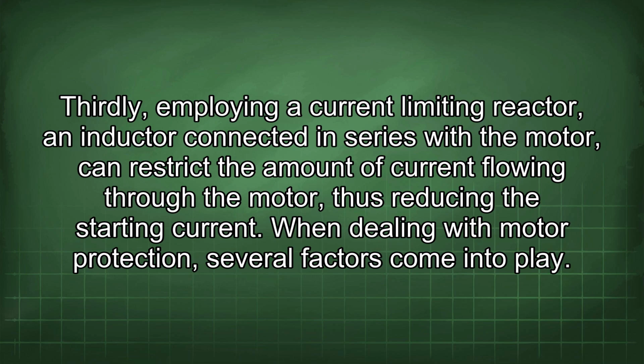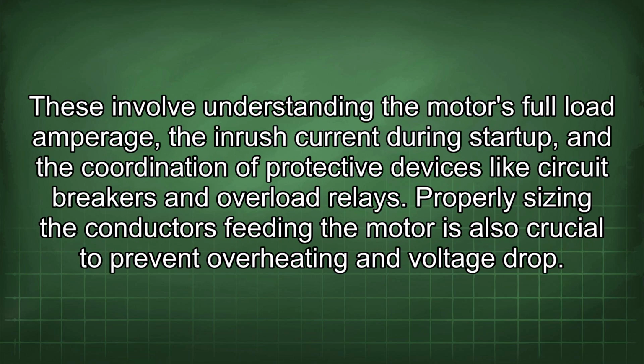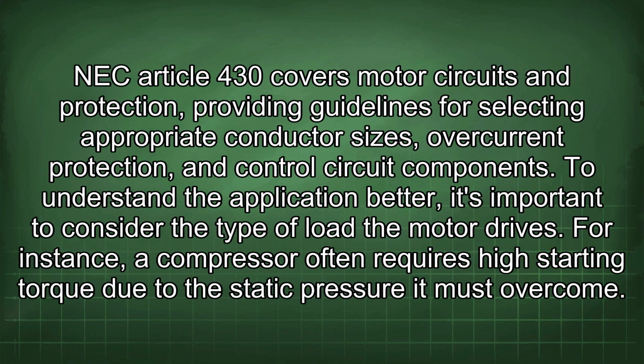When dealing with motor protection, several factors come into play. These involve understanding the motor's full load amperage, the inrush current during startup, and the coordination of protective devices like circuit breakers and overload relays. Properly sizing the conductors feeding the motor is also crucial to prevent overheating and voltage drop. NEC Article 430 covers motor circuits and protection, providing guidelines for selecting appropriate conductor sizes, overcurrent protection, and control circuit components.